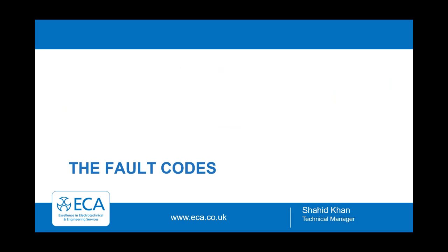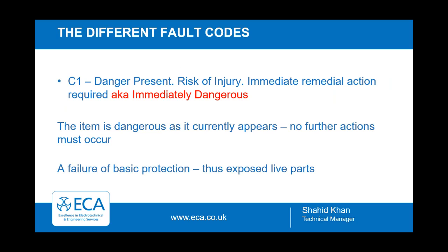The fault codes. So a C1 code is an item which indicates danger present, risk of injury and immediate remedial action required, also known as immediately dangerous. Basically, as the item currently sits, it is already dangerous and must be acted upon. No secondary process must occur to make it more dangerous. Another way of looking at it is that the item under investigation is an example of a failure of basic protection, exposing live parts which need to be live to perform their function.